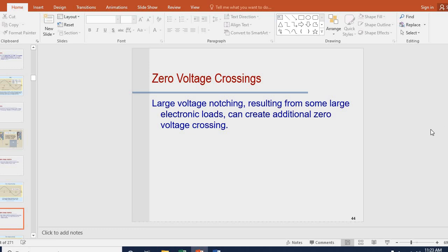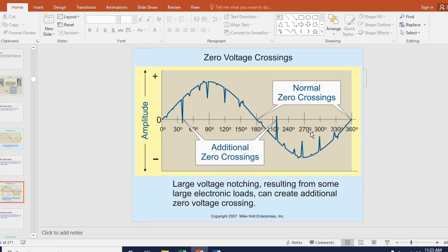All right, if you have some large loads, they can create additional zero voltage crossings. Well, if you've got a device that's looking at how many times that voltage crosses zero, it could give you false readings. And sometimes they use that for counters and other devices, but with large loads, you have to use some electronics to filter out that notching. It shows some of your notching right here. Normal zero crossing is at 180, but it crossed it here 1, 2 times. So you would have 1, 2, 3, 4 crossings if you had a device that was counting the times that the sine wave went to zero.